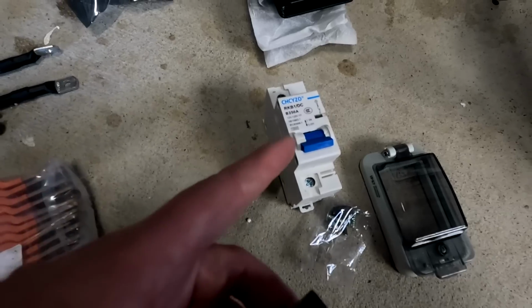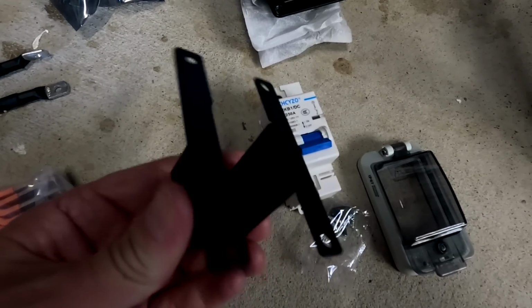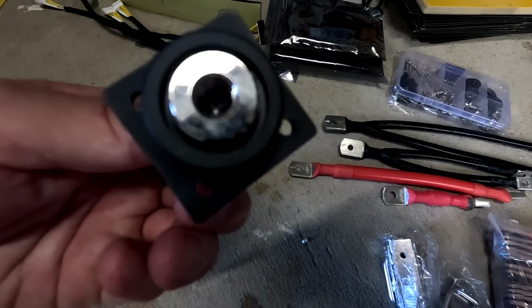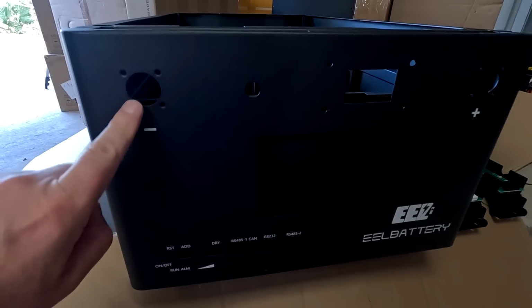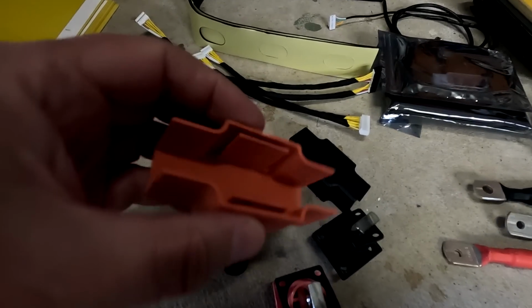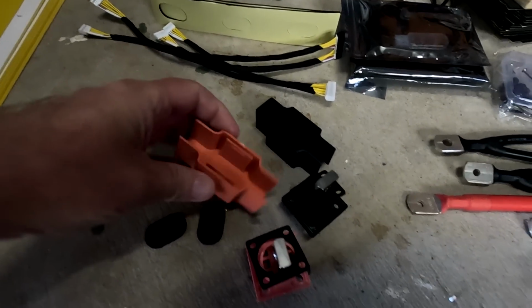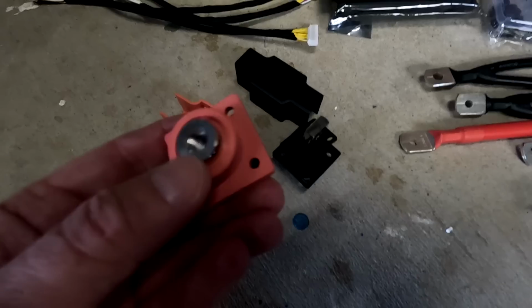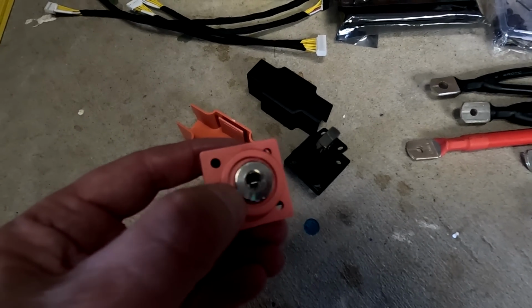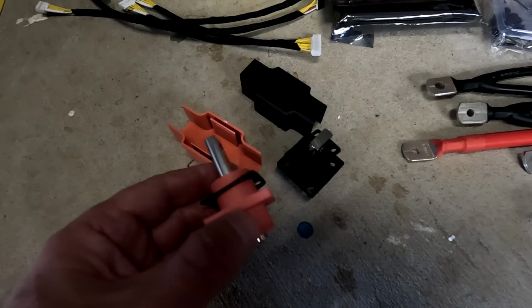Okay, and the breaker also comes with this mounting bracket for the front plate, some screws. We've got the usual M8 terminals, but as you can see, we have only 1 terminal each, but this plastic cover comes with 2 outlets. So if you have more than one of these boxes, you have to wire all your connection cables between the batteries to 1 terminal only.